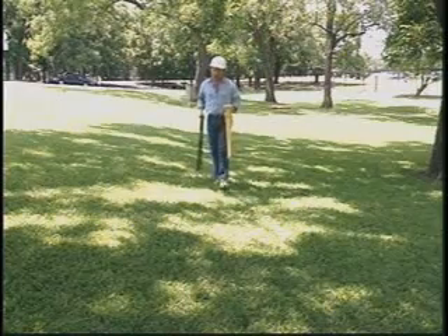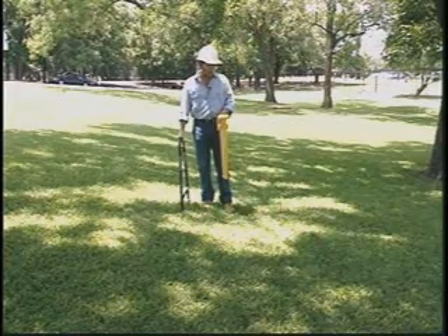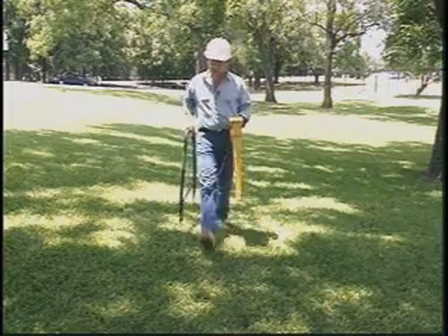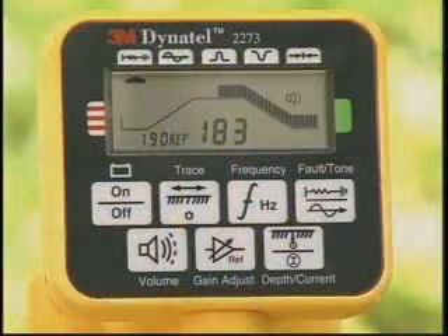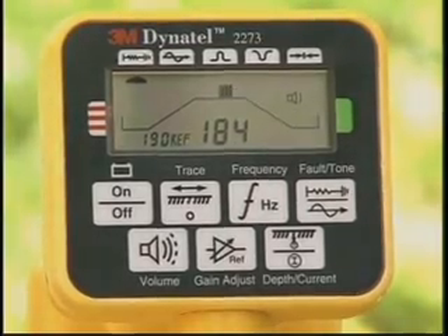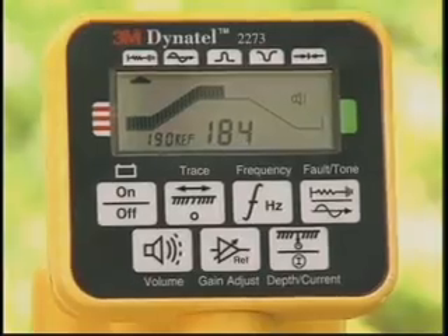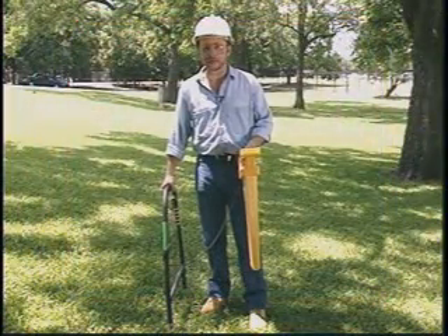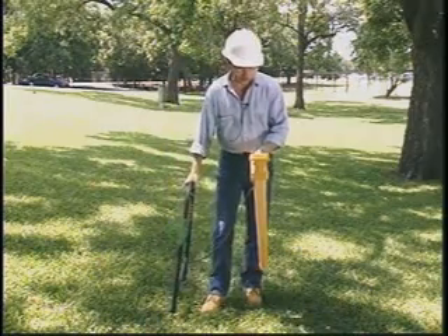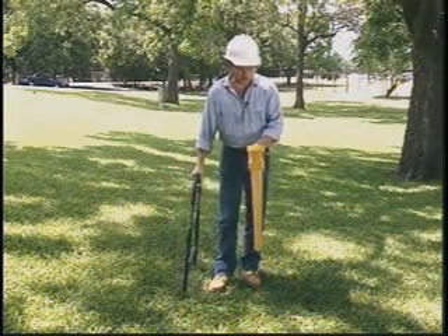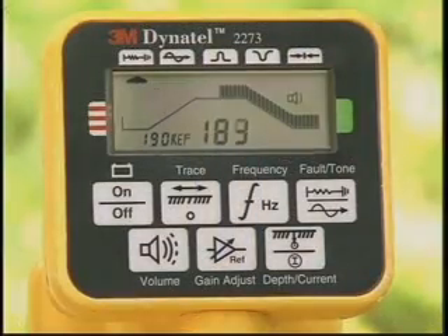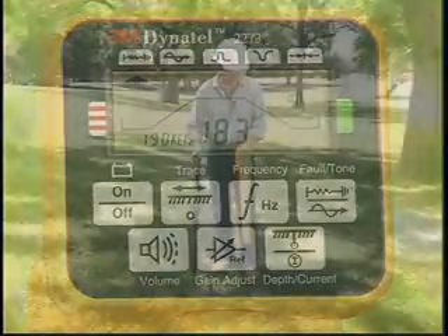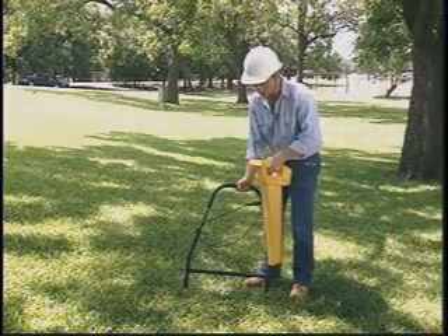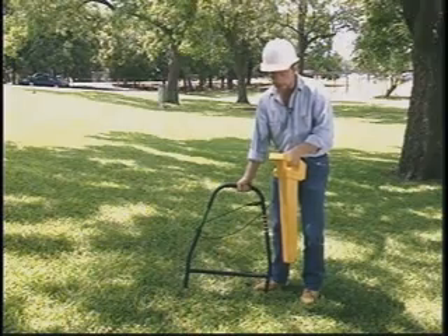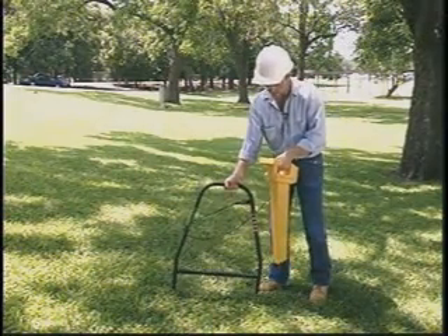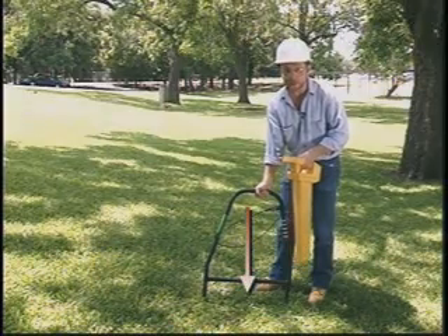Continue along the cable path, inserting the frame probes every few steps while watching the receiver's bar graph. When you pass the fault, the bar graph changes from the green to the red stripe side. The fault is now behind the earth contact frame. Back up slowly, inserting the frame every few inches until the bar graph returns to the right or green side. When the bar graph changes from one side to the other, turn the frame 90 degrees to the cable path. When you locate the point of bar graph reversal, the fault is beneath the center of the frame.